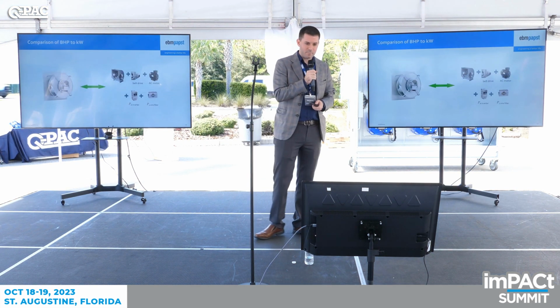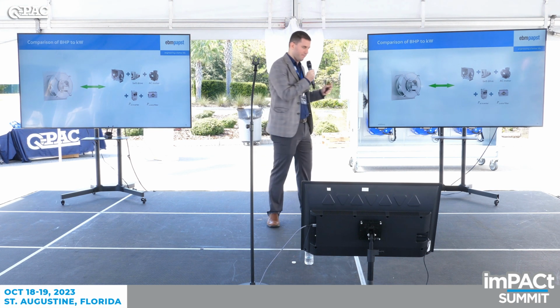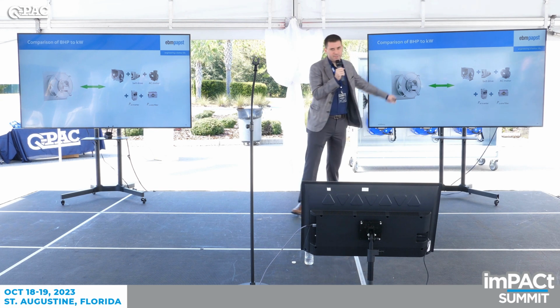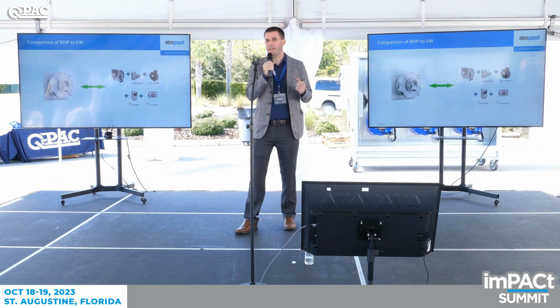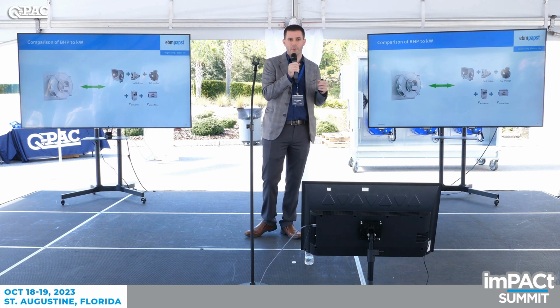All right, so comparing kilowatt to brake horsepower. When we give you a kilowatt, any of the EC fan manufacturers, they'll give you a kilowatt. It's for everything you see in the picture there. So it is the actual electric input power required to spin that whole assembly, including electronics, including wheel, including motor. When you get a brake horsepower, that is the power needed to spin the wheel at that operating point. So it doesn't factor in any belt drive, AC motor, any filtering that you have in any VFD.